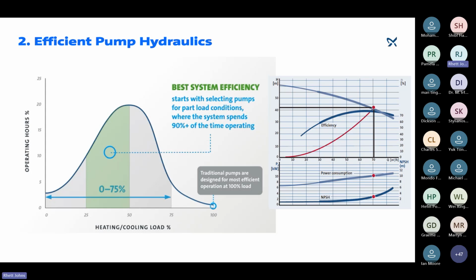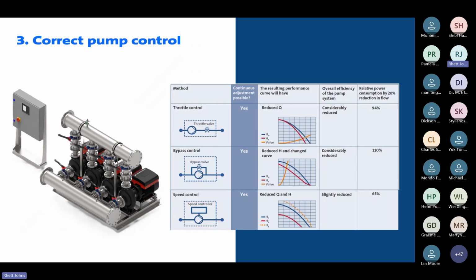And a common method to add efficiency to pump hydraulics would be to have a look at the best efficiency point of the system, and split the flow of your system over multiple pumps, then switching off the extra pumps as your flow demands reduce, so that it's continuously running at the top end of efficiency per pump. This is an example of a multi-pump system on the left. Sorry, Charlie, back to you.